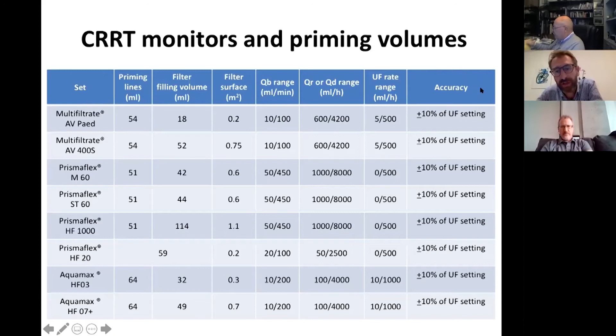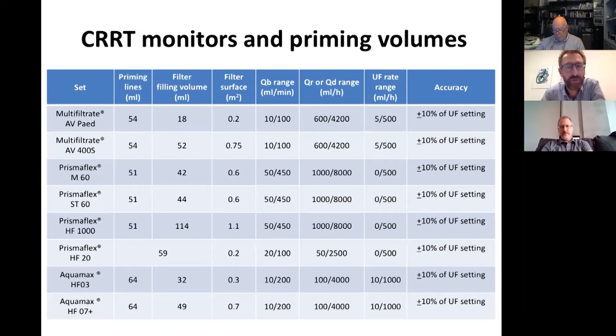The other point from this table is the accuracy. In most of these machines, the accuracy is set at plus or minus 10% of the ultrafiltration setting. So, for example, if we are prescribing an ultrafiltration of 1000 ml over 24 hours, this may result in achieving 900 or 1100 ml over 24 hours. That's not a small difference when treating very small infants. So all these problems have been tackled by the Carpe Diem.